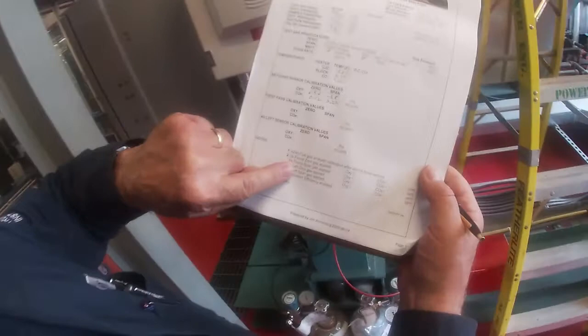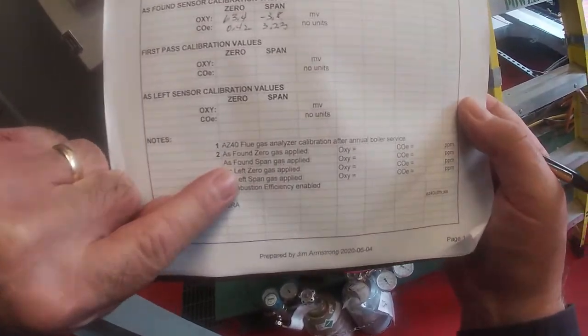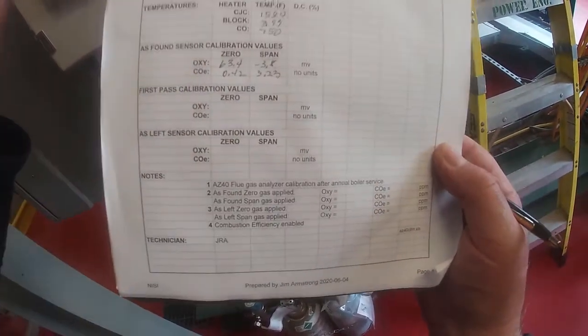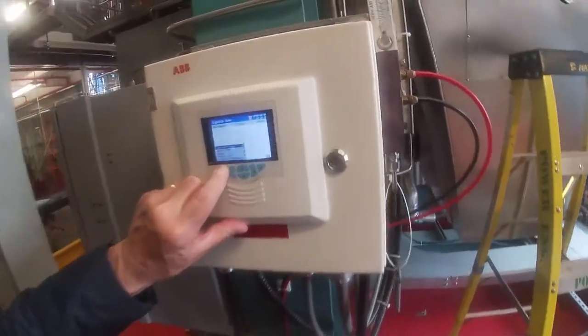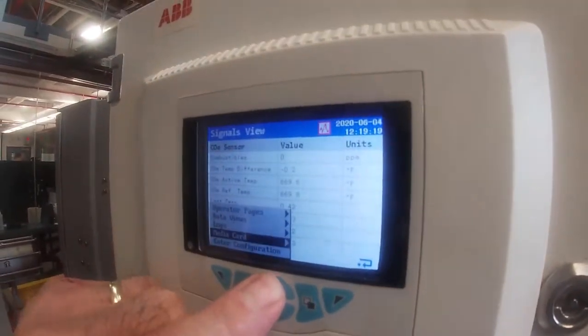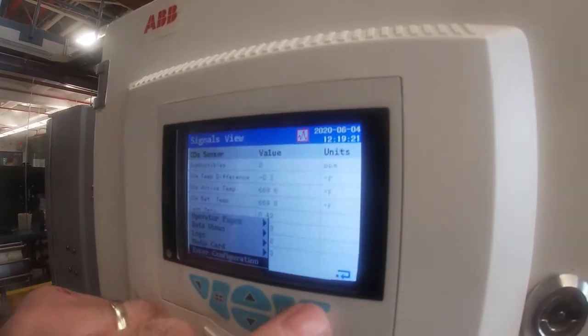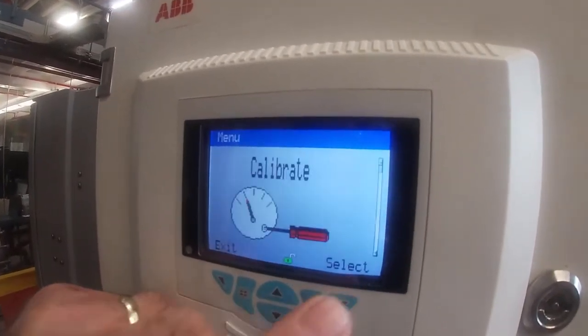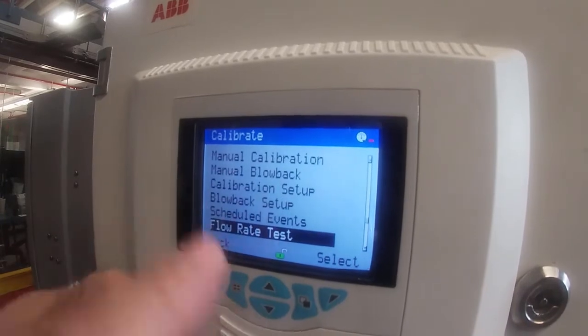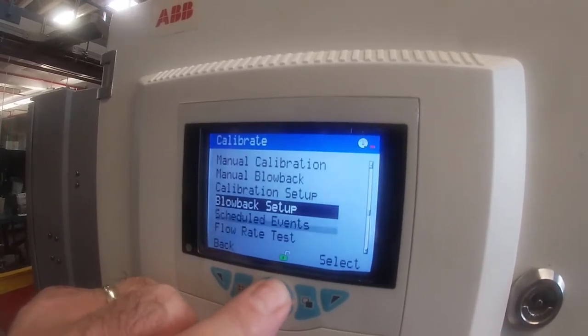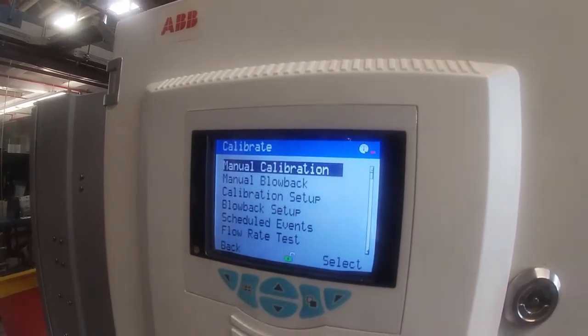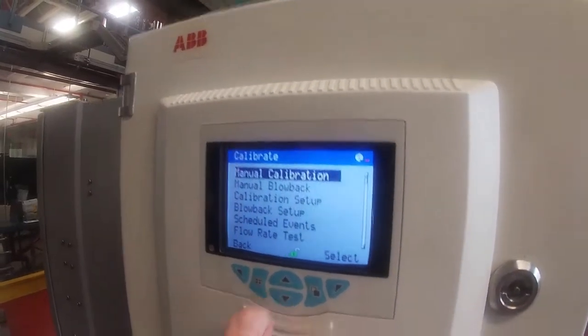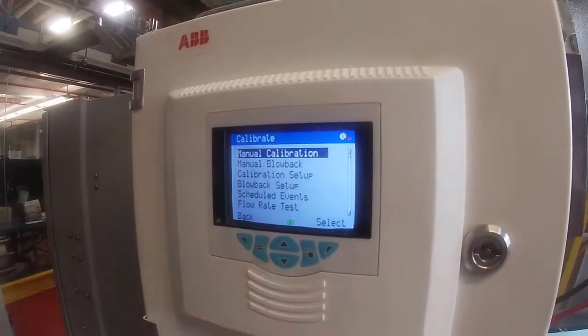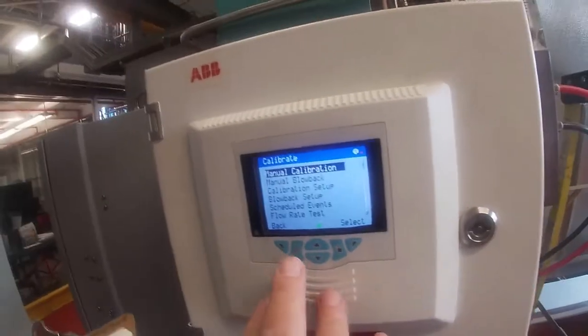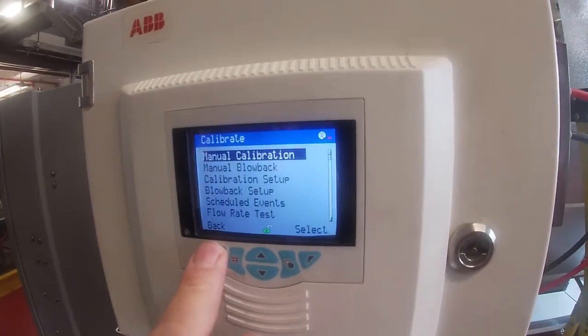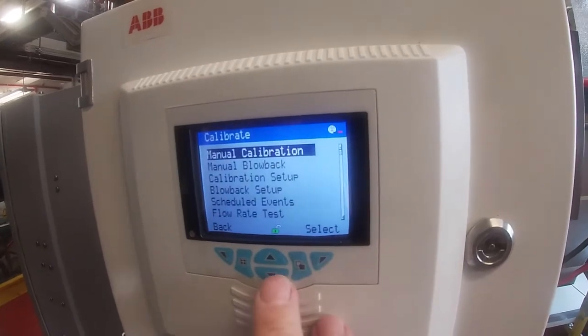Okay, the next thing we need to do is an as-found zero test and span test. So I'm going to bail out of here, back screen, go to configuration, enter, advanced. I want to go into calibrate. Now I'm going to do a manual calibration, but we should first check to make sure that the gas samples are set up properly. So let's go back for a second.